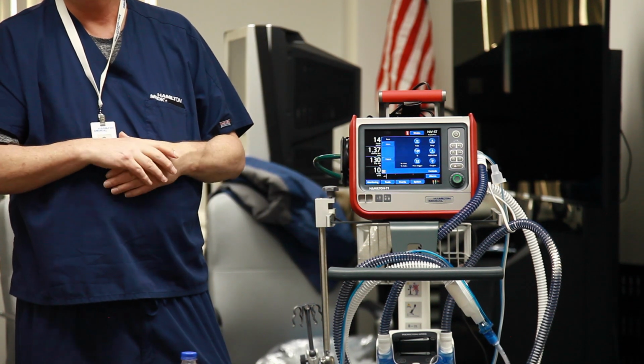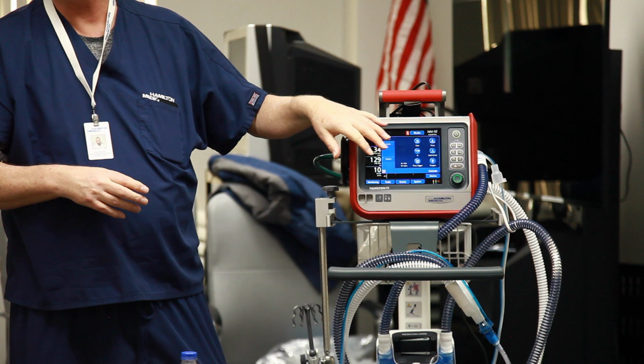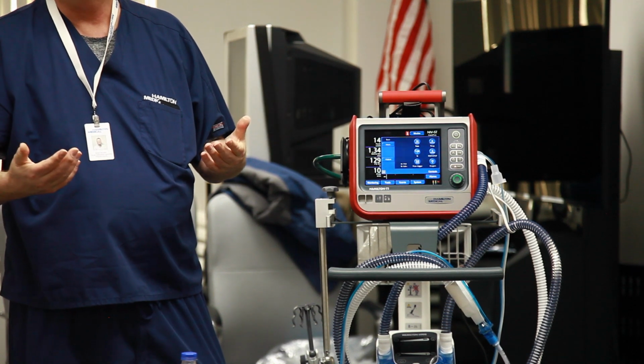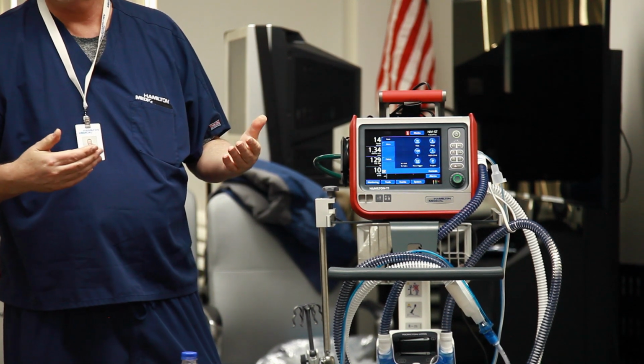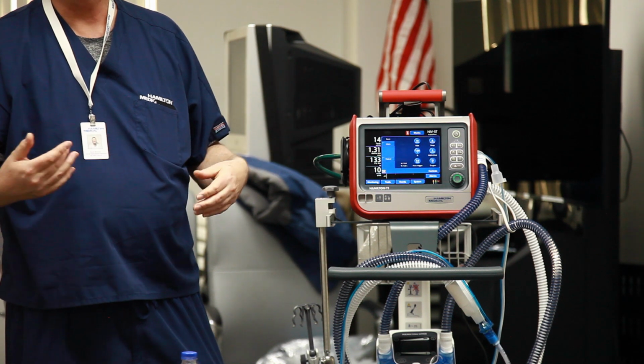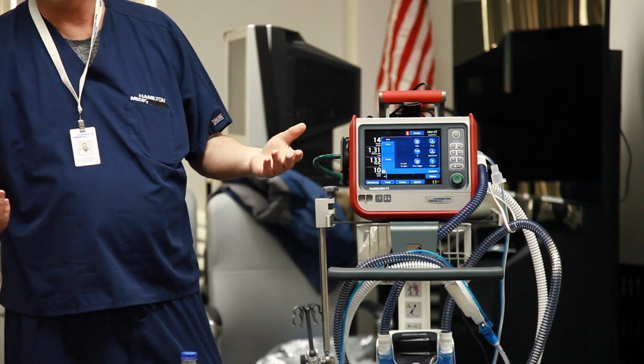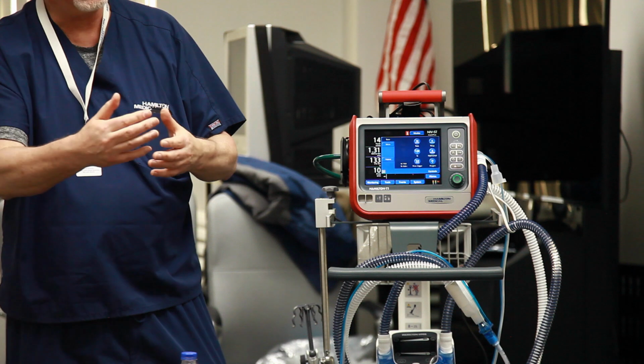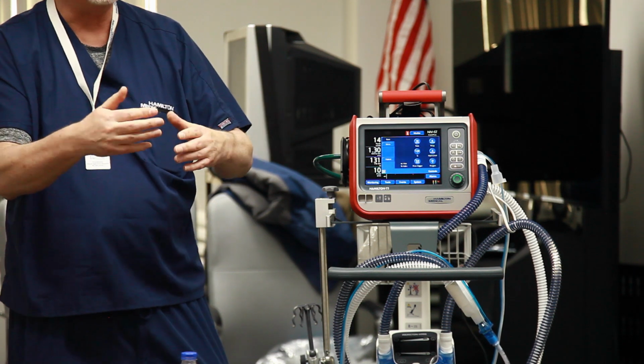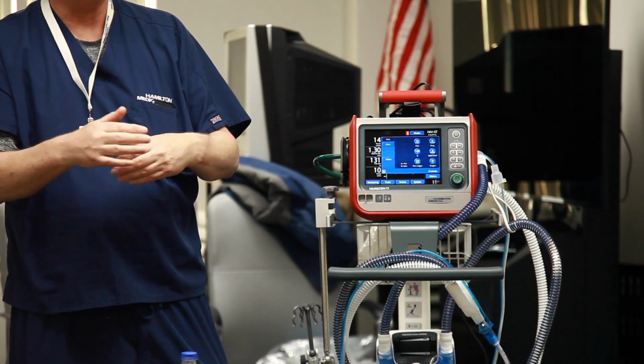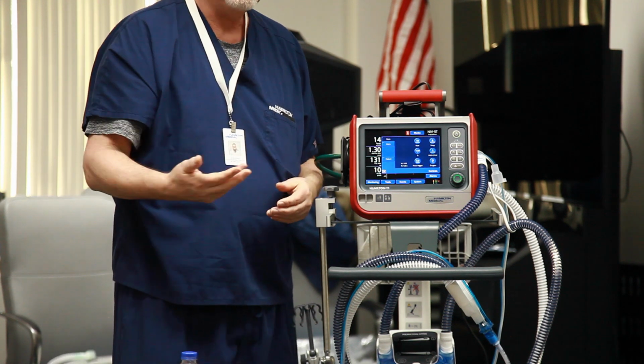So we set the backup rate. You set the backup rate for each patient, configured with the height. But you want to look at that. You don't want to have a crazy rate, like 20 or something like that, on a patient that's breathing spontaneously, because it's going to be uncomfortable with that set inspiratory time every once in a while.